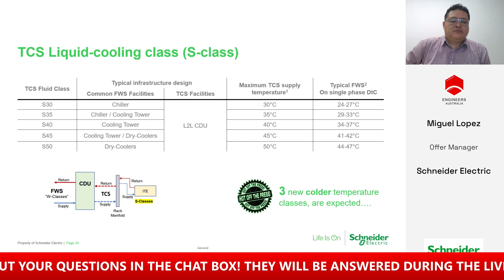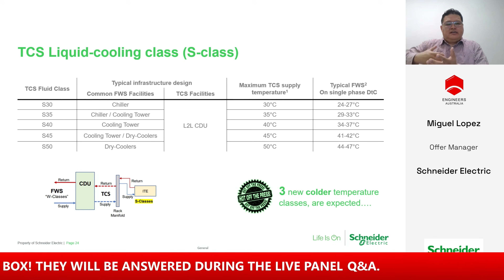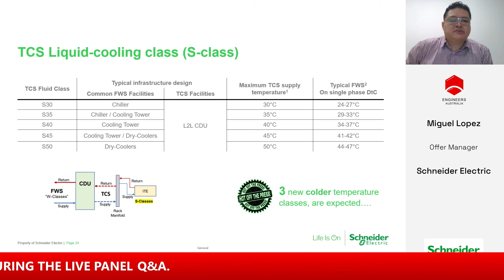In 2026, probably 2027, in the next couple of years, if not earlier, we will see a significant trend from S50 down to probably S45, S40, even S35 and S30 water temperature thresholds on the TCS loop. And as you can see, the second column from the left shows that whereas we could get away with dry coolers on an S50 TCS water temperature, as we approach S30, you now need mechanical chillers. So you will need the efficiency aspect of running free cooling modes of operation as the water temperature takes a dive, because the NVIDIA chip manufacturers' heat output is so great that we now need to temper that with lower water temperatures. It means that you may not be getting the same free cooling hours that you were enjoying previously.